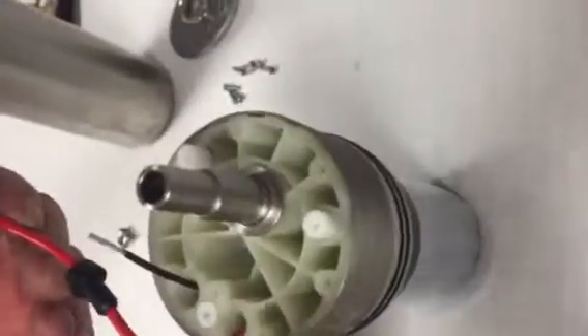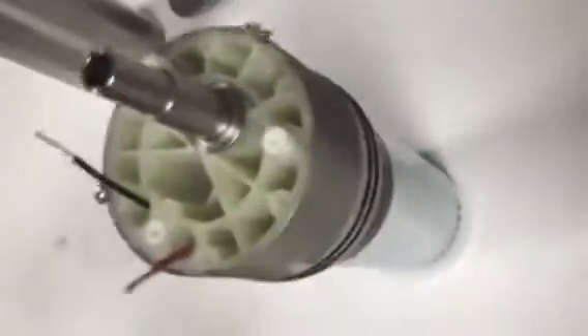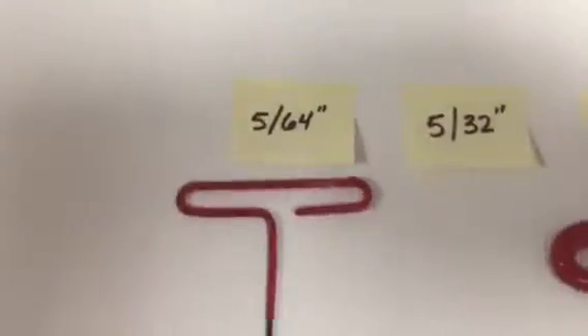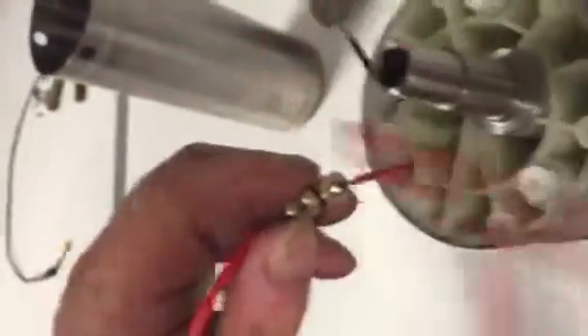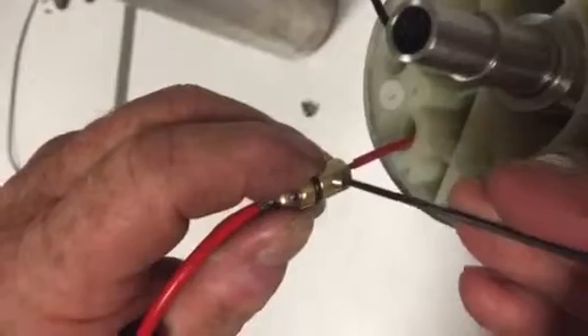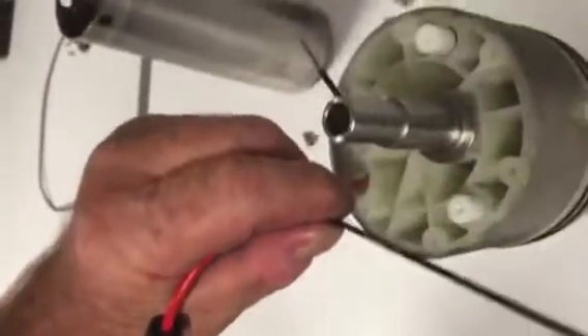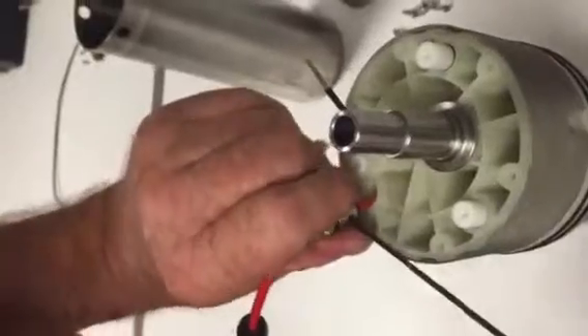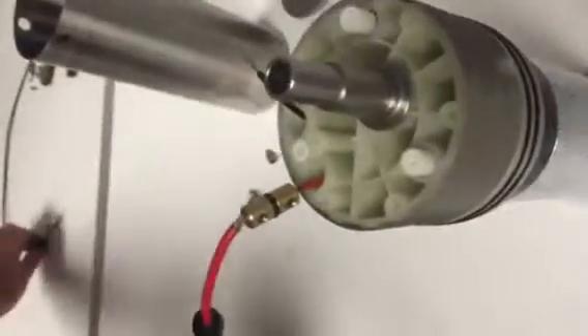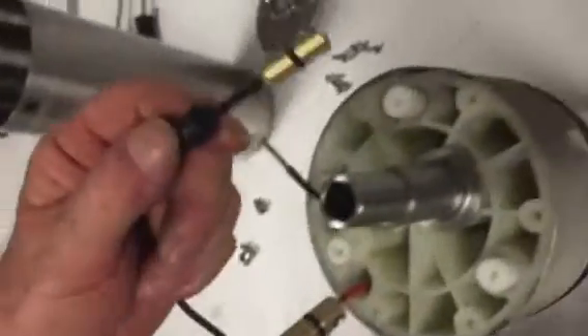We're going to proceed now with our wire interconnection. So the anti-wicking plug, you want to make sure, of course, to tie red to red and black to black. The anti-wicking plug can now be secured with the 5/64 wrench, and we're going to put the wire into the anti-wicking plug, and there's a little Allen that you will tighten. Firmly tighten. Secure that crimp, if you will. Black to black in the same manner.